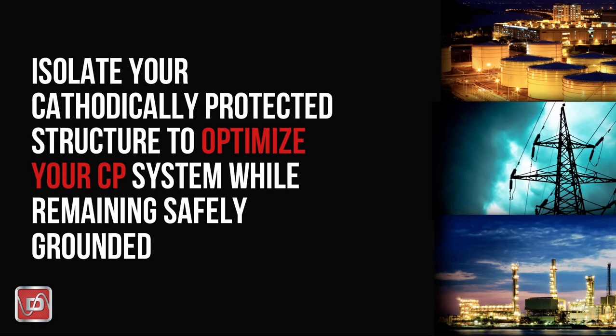The same concept can be applied to a wide variety of applications, including decoupling tank grounding systems, decoupling electrical equipment, insulated joint protection, and many more. You can use a Dairyland DC decoupler to isolate your cathodically protected structure from the grounding system or from other equipment, to optimize the performance of the CP system while still retaining all of the safety grounding and bonding required.